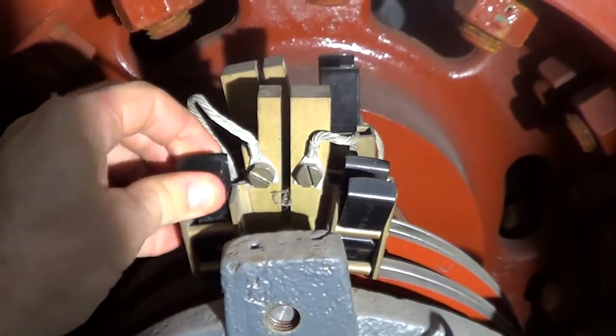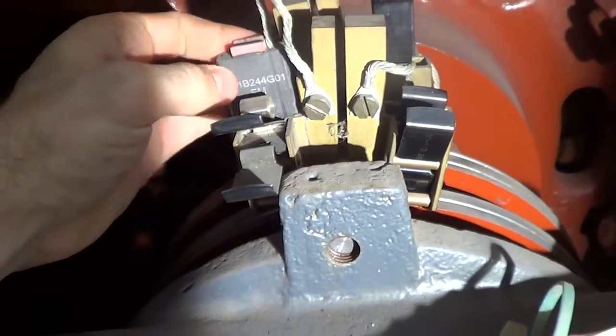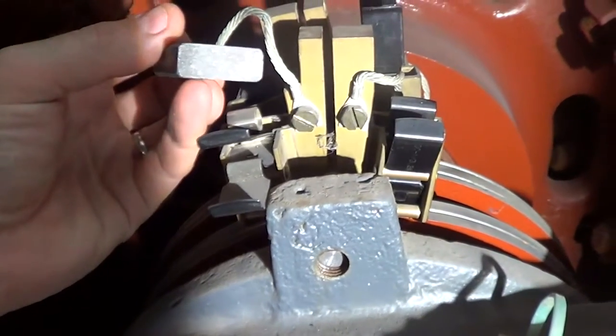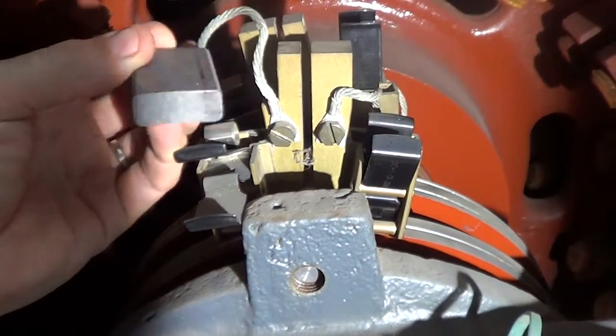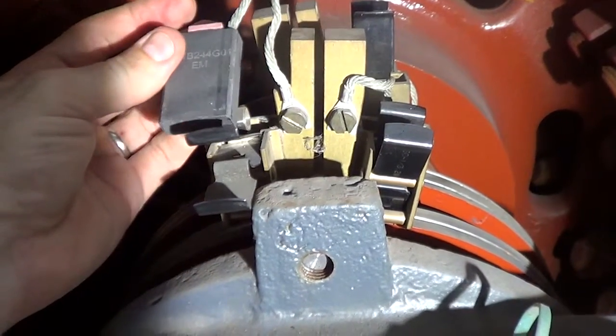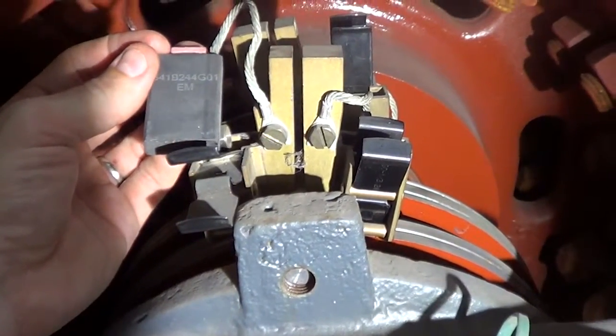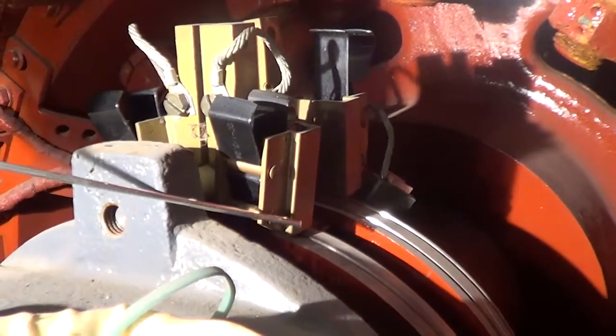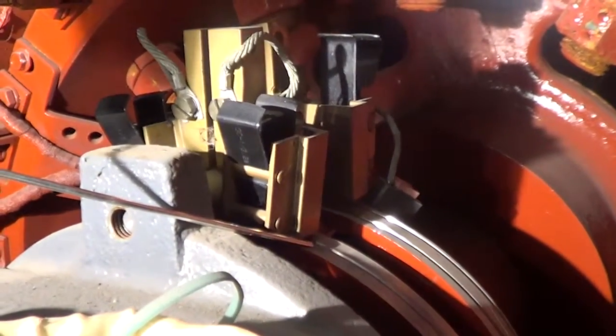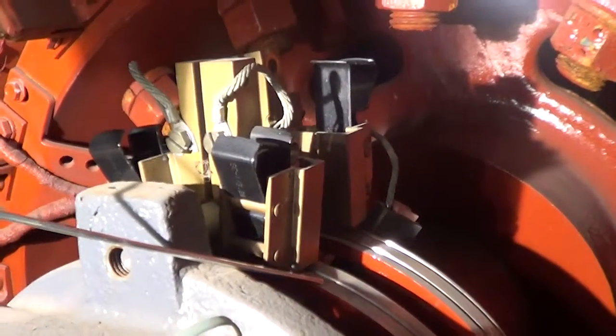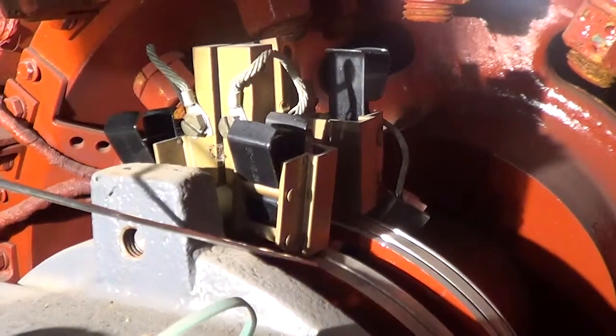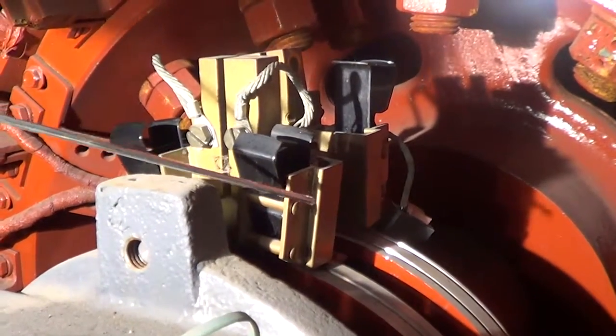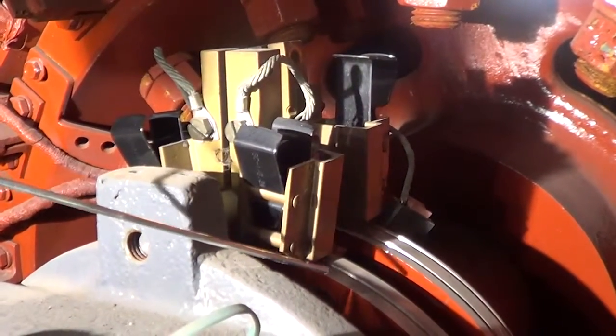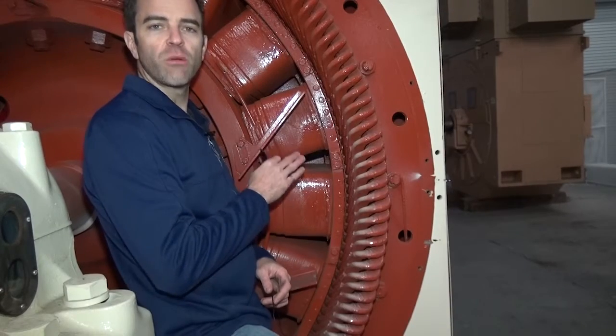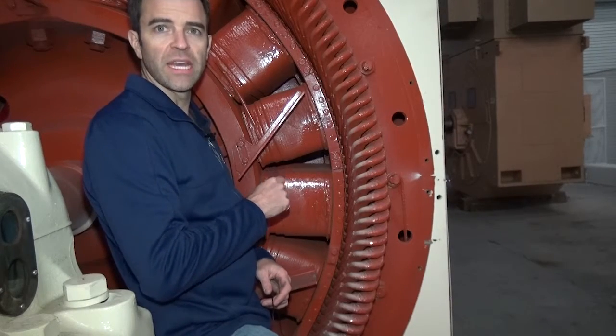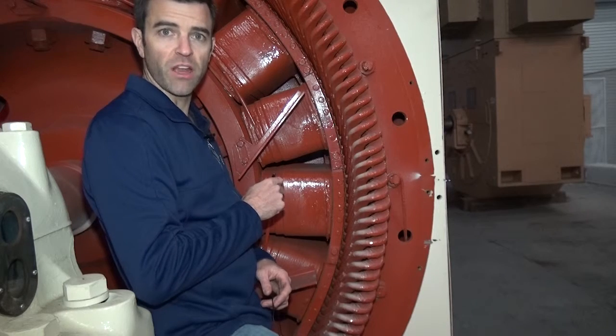Remove all brushes by pinching the spring and pulling the brush out. Check the length of the brush and also inspect the wear face for any signs of foreign contaminants. If the brush has been severely depleted, replace it with one of the equivalent part number. Between the collector ring and the brush holder, there is a small gap, and this must be measured for all brushes. This distance is critical, as too large of a gap will tend to cam the brush, which will cause chatter and early failure. Let's talk about some of the details of the rotor assembly and some inspection parameters we want to have a real careful look at.